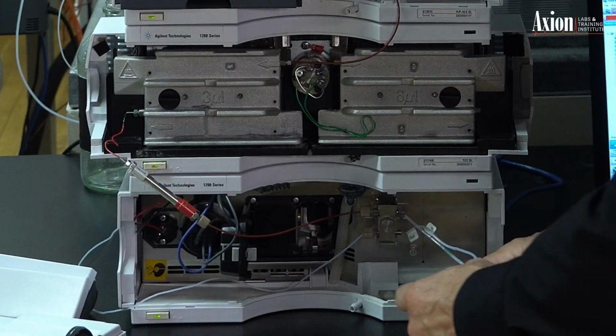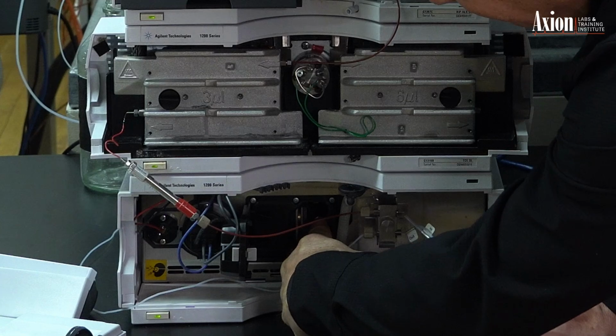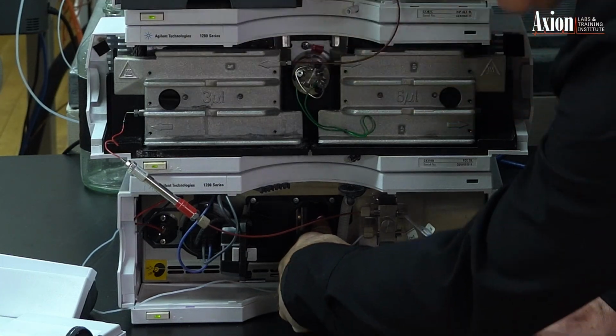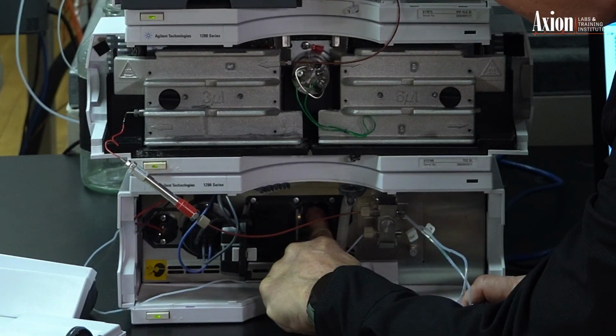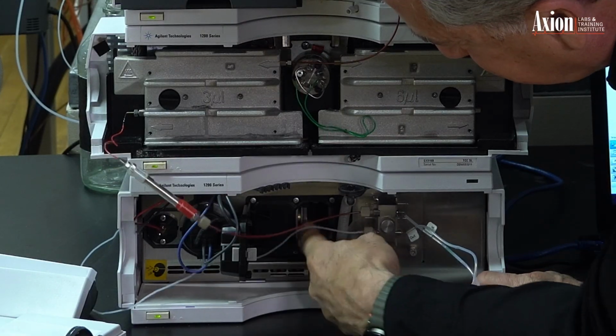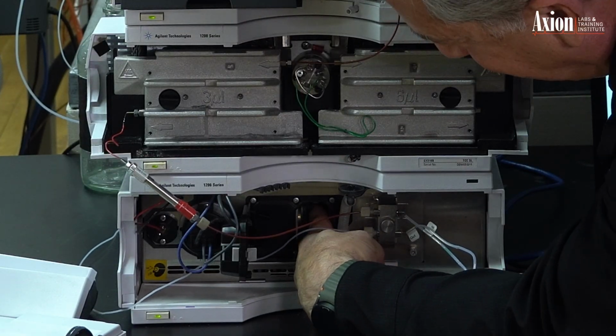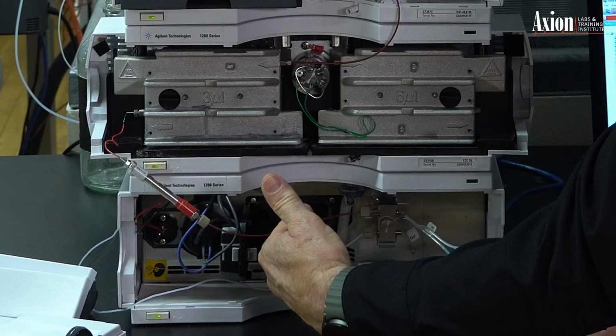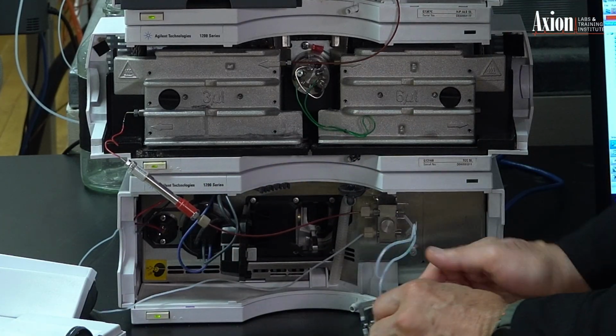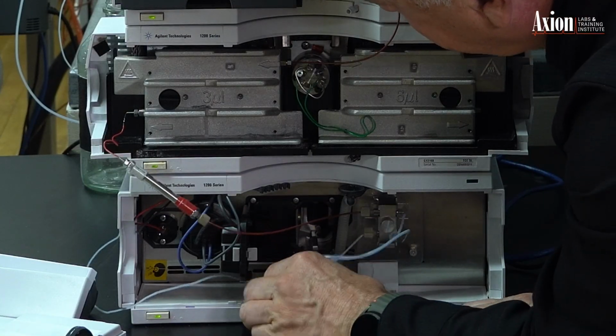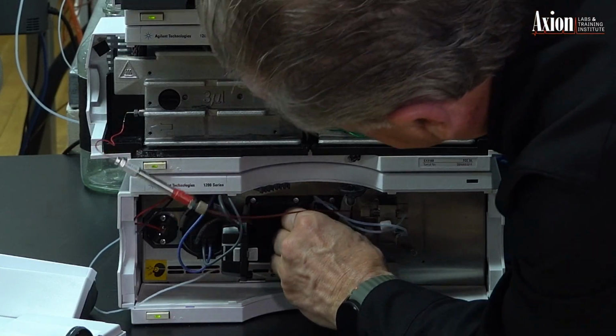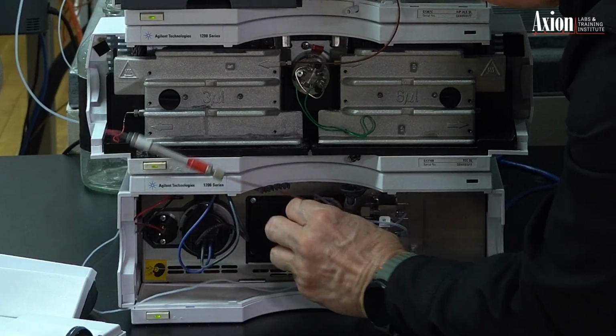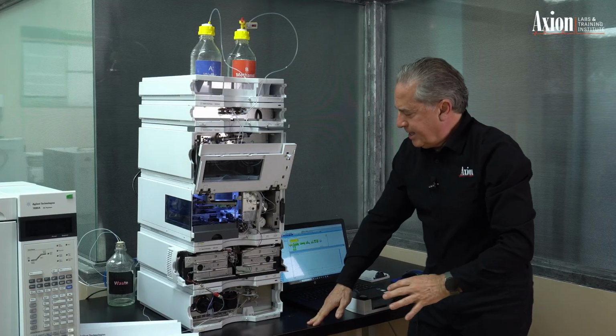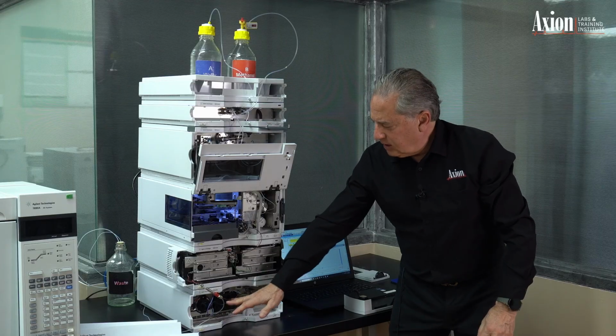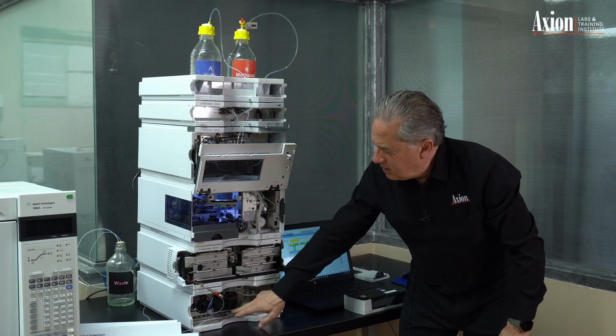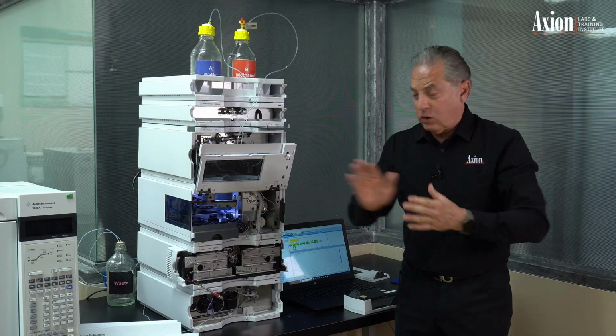Now, if you look inside, I don't know how well you're going to be able to see this, but if I put my finger here, hopefully what you're seeing is a little bit of light bouncing off my finger. You might not be able to see it, but trust me on this one. There's a little light back there, and that's the UV light. So it's coming through, it goes through the flow cell, and then the detector's on the other side. So put this guy back in. There we go. So if I close it back up, the flow is continuing through the flow cell, and then from the flow cell, it goes out to the waste bottle.